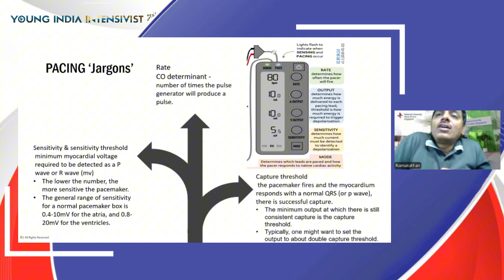For the sensitivity threshold, as I said, it is the minimum voltage required to be detected when the pacemaker starts sensing for myocardial depolarization. So what you should do is set the pacemaker rate below the endogenous rate if present and place it in one of those modes. Then the sensitivity number is increased, which essentially means the pacemaker is becoming less sensitive. The higher the number, the more voltage the pacemaker needs to detect before it senses. So you make the pacemaker less sensitive till the sense indicator stops flashing.